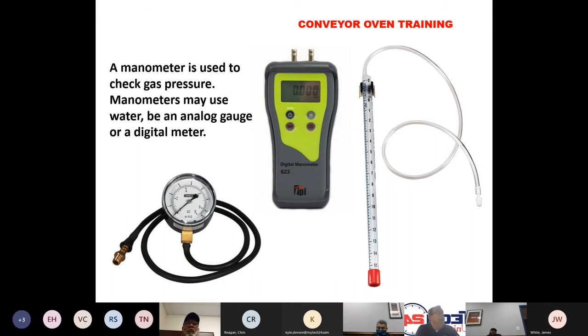So these are different types of manometers that are used to check gas pressure. They may be a water manometer like that one on the right. You may have an analog gauge, or you may have a digital manometer. There are a couple of the Middleby Marshall ovens, the 540, the 640, 740, the 40-inch range, that you will have to have a digital manometer to set the pilot pressure, because it runs between about 0.4 and 0.5 inches of water column. And you're just not going to see that accurately on a water manometer or a gauge manometer.